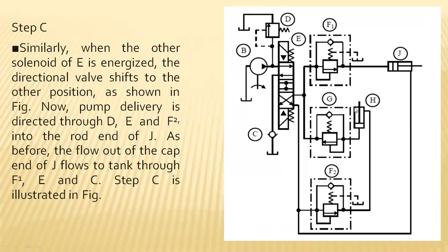After full extension, there is no allowable vacuum or volumetric condition to enter the fluid further in the cylinder and piston arrangement of this H actuator, and hence that pressure will return back towards the F1 sequence valve, which is opposing with respect to the check valve here, and finally the sequence valve will come into force by compression of the spring, and the set pressure will enter into the J. So that is the condition in the first step.